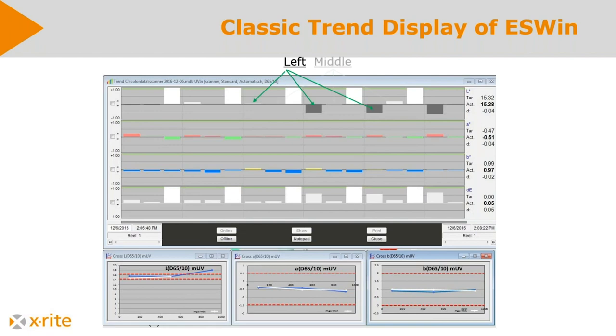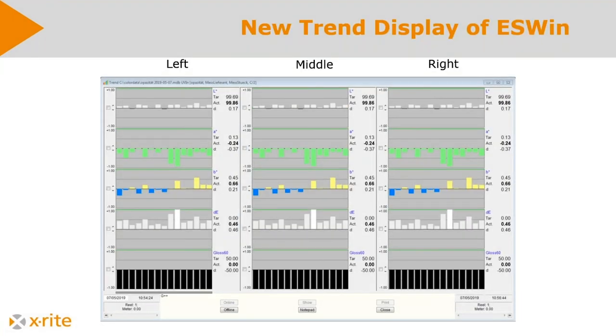This is how the software looks like. So we have two different views. Some people like one view, some people like the other view. This is now a view where you see these measurements left, middle, right on a diagram, and you can see the last, whatever you set up, 10, 20, 50 scans, whatever you want. And on the bottom, you see basically the profile of the measurement. You see on the left-hand side the L value, last measurement, and the measurement before, the A value and the B value. Or, if you like it, we can have three screens or three graphs, let's say, where you have left side, middle side, right side.